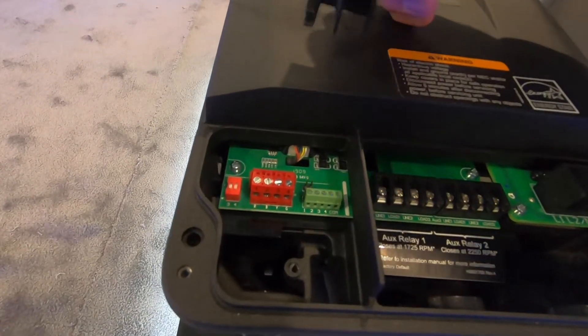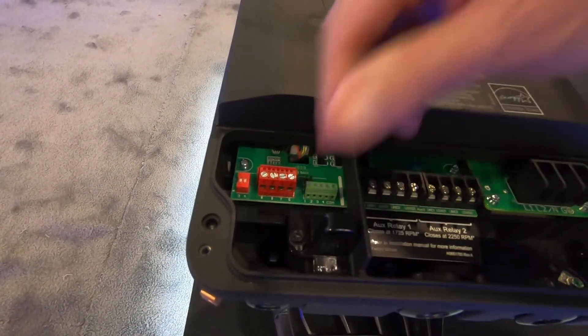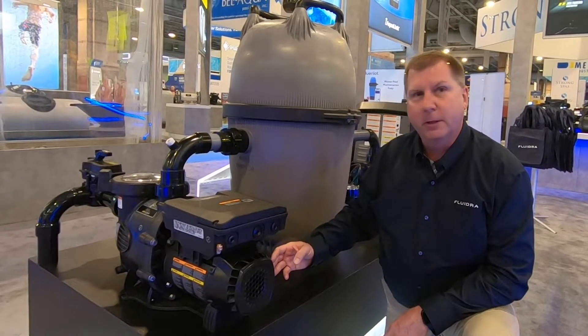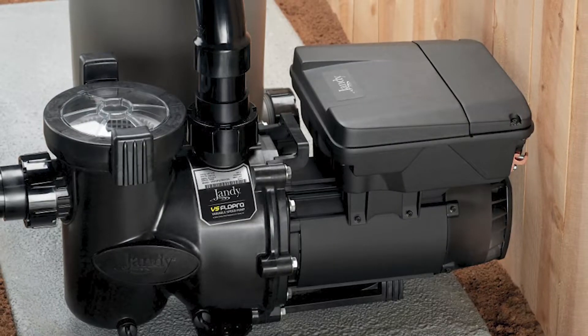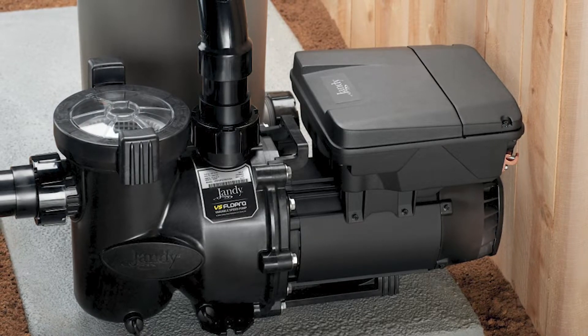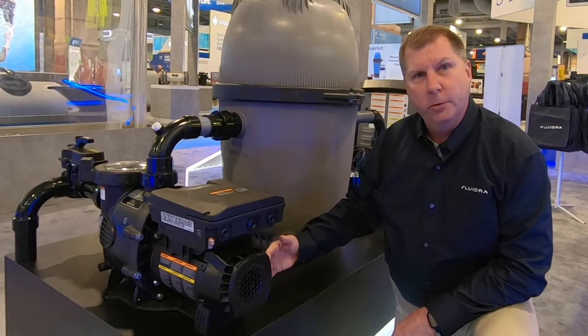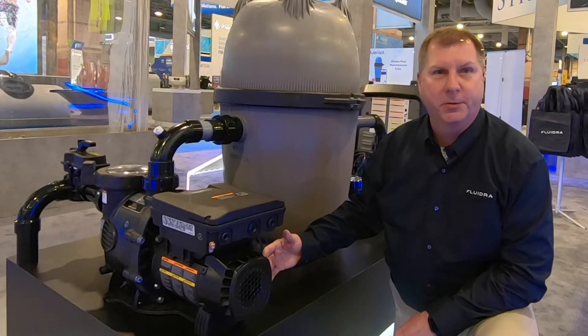Last but not least is an RS485 quick connect port for easy installation and maintenance. The new motor platform also features a zero clearance totally enclosed fan cooled motor for installation in tight spaces. The zero clearance fan allows you to put the pump right up against a foundation or a fence, as all the cooler air to keep the motor cool is pulled in from the sides of the motor, as opposed to the back of the motor.